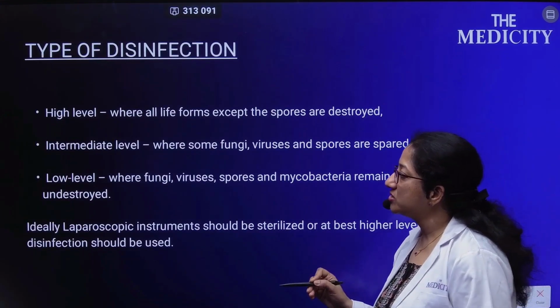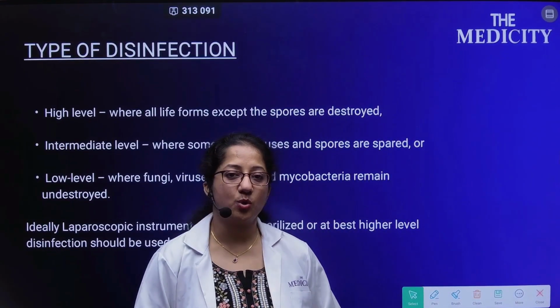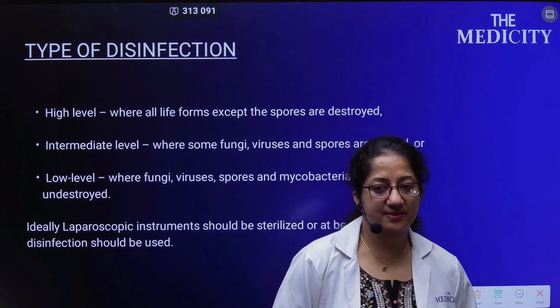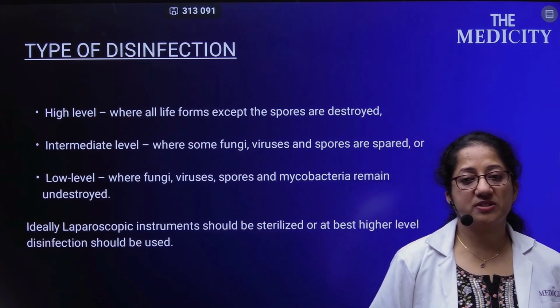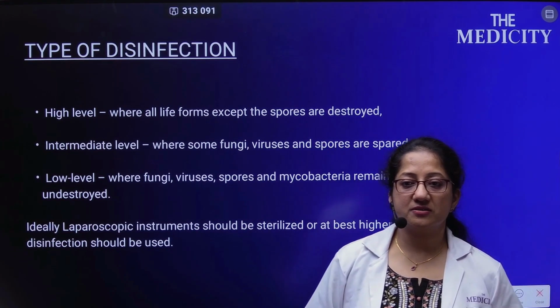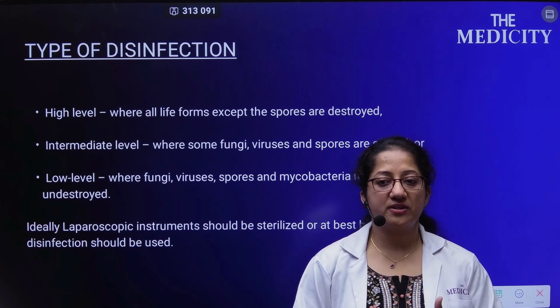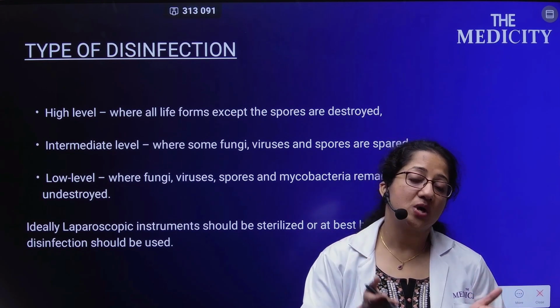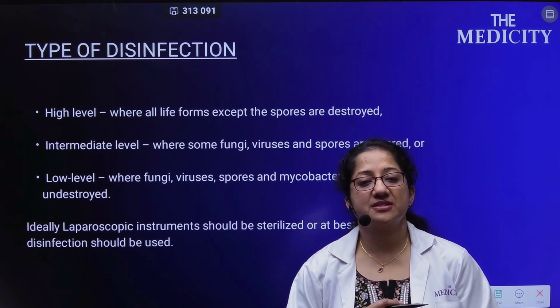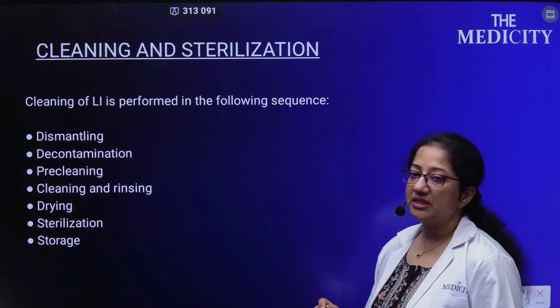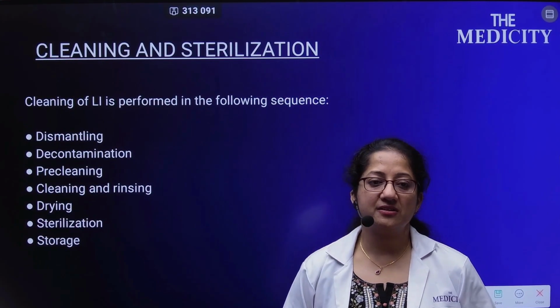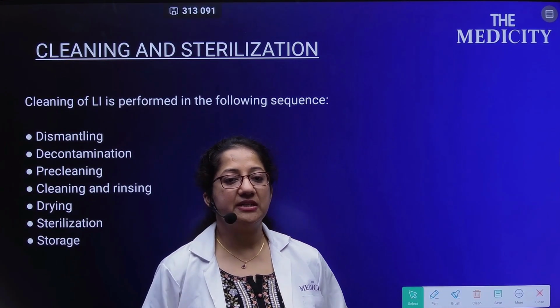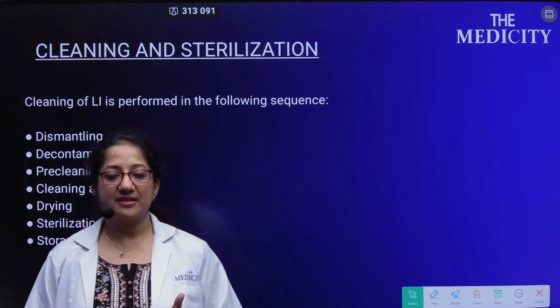Disinfection, basically high-level disinfection, is where all forms of life except the spores are destroyed. Intermediate is where some fungi and the viruses are spared. And low level is where the mycobacteria remain undestroyed. So ideally in the laparoscopic instruments, the sterilization should be of the highest level. Cleaning and sterilization includes dismantling, decontamination, pre-cleaning, cleaning and rinsing, drying, sterilization and storage.